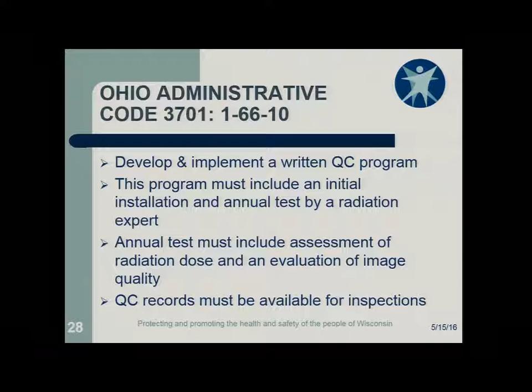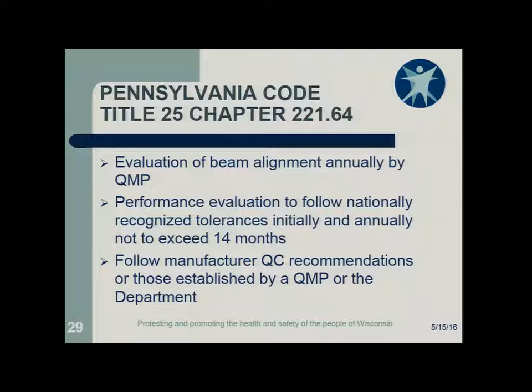Pennsylvania, this is still proposed. I meant to add that to the slide, but it was in my beginning. Evaluation of beam alignment annually by the qualified medical physicist. Performance evaluation to follow nationally recognized tolerances initially and annually, not to exceed 14 months. Follow manufacturer's QC recommendations or those established by the qualified medical physicist or the department.